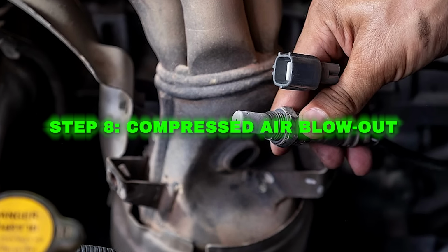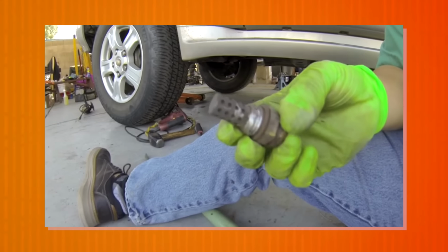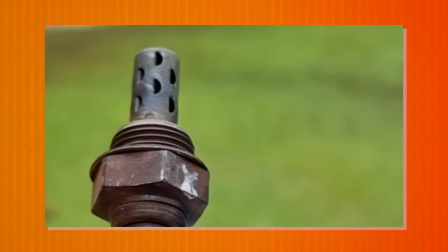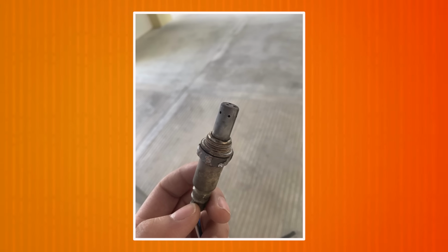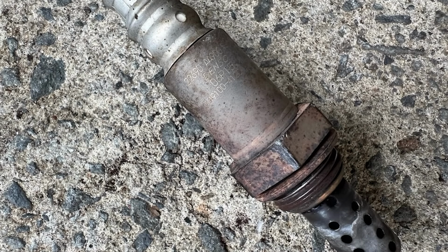Step 8. Compressed air blowout. Hold the sensor with the sensing element pointing down and blast compressed air into the ventilation slots for 10 to 15 seconds, rotating the sensor as you go. You should see loose particles blowing out.